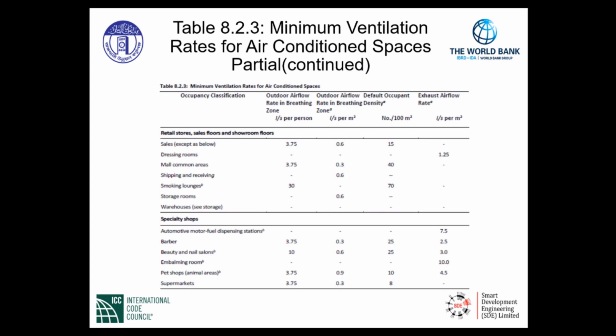Now further, this particular specialty shop also requires an exhaust airflow rate. And as seen in the very last column, it is 3 liters per second per square meter of floor area that is used as beauty and nail salon area. So as we look into these categories and the values in the table, we should be familiar with how to pick the values from the table and then utilize them in upcoming equations to calculate the total amount of outside air required for the zone.